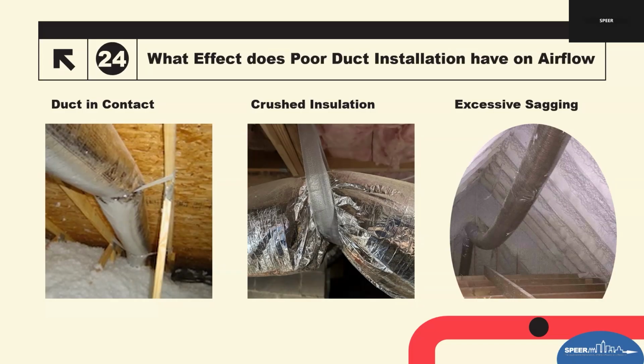And then on the right we see sagging ductwork. We should not see more than a 1/2 inch every foot, so basically 2 inches per every 4 feet sagging. That's way more than that. We should have another strap. Looks like there was another strap at one point. Somebody either cut it or it broke, hanging off the ceiling rafters there.